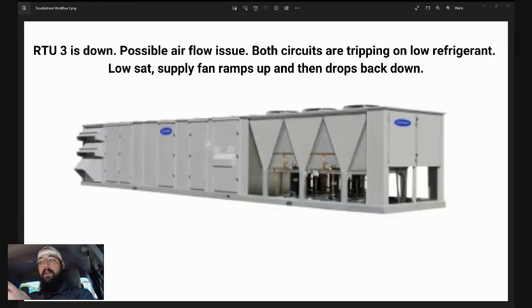Now, what that would do to us is the relay for the supply fan could be the weak point in that process. So the first thing we identify is the fan dropping in and out. We go to the output of the controller that runs that piece. We see, is our output what's actually changing, or is it at the relay itself? We see that we maintain the output. Let's say the output never drops, but our voltage does. Well, that could be a transformer issue. That could be a coil issue on the relay or the contactors. If we've got an old relay that's got a coil on it that's getting weak, but maybe the contactors aren't as dramatically affected by that voltage, they can run down to that low of an input voltage when they're a good, fresh, strong coil.